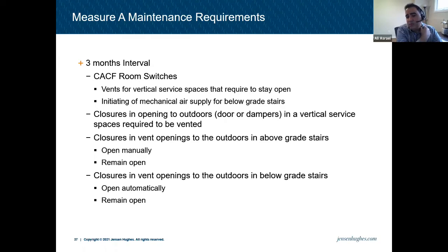Okay, so again, measure A, requirements for above grade stairs: you don't have to have an automatic door opener, right? As long as it's manually openable and it can remain open. That's important, that it can remain open. Because it's manually openable, but how do you want to keep it open? There should be something there to help with that. And for below grade, the same thing, they open automatically and they can remain open. These are actually the maintenance requirements for measure A, right?